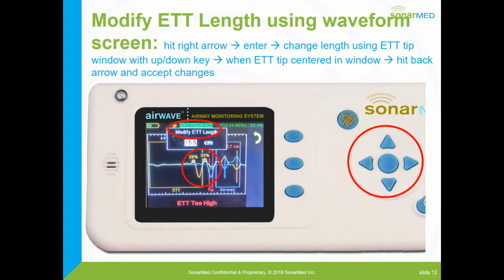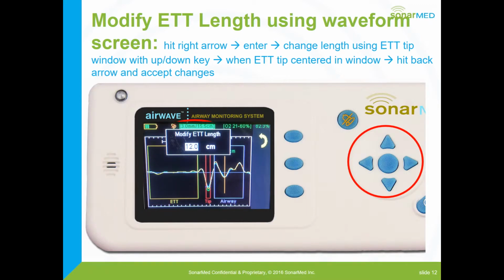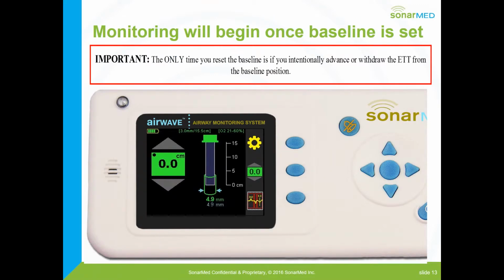So again, you see the yellow on the left, and as I decrease the length of my endotracheal tube, I now have the echo in that red box with the green little circle at the very bottom. I use my back arrow at the top, that top oval button, and I'm going to confirm, okay? And it's really important, as we start monitoring now, that the only time you reset the baseline is when we purposefully reposition the endotracheal tube. That's the only time you're going to reset a baseline.